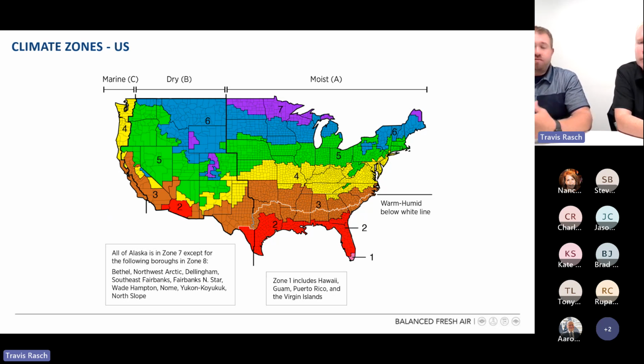If you asked that question maybe even 5 years ago, I would certainly still probably be hedging towards an HRV. The thing that has changed over the last probably 5 to 10 years is our ability to deal with moisture inside an ERV core in those colder climates. Like Chicago, Illinois, or Minneapolis, Minnesota, or Milwaukee, Wisconsin, where we're located near. Our ability to keep that core from turning into an ice cube. So if you can imagine that ERV, we talked about that moisture vapor, or that latent component, we're going to be retaining some amount of moisture.